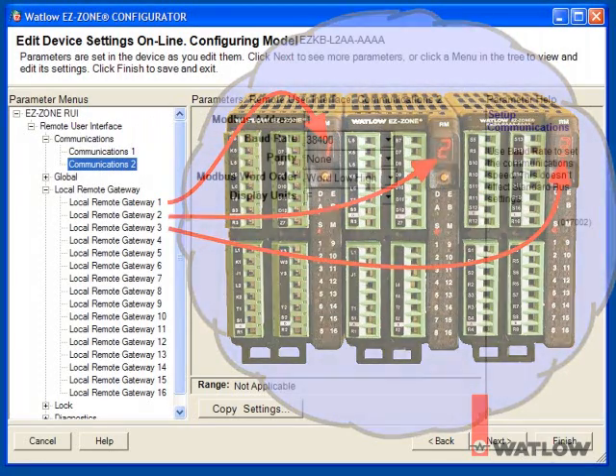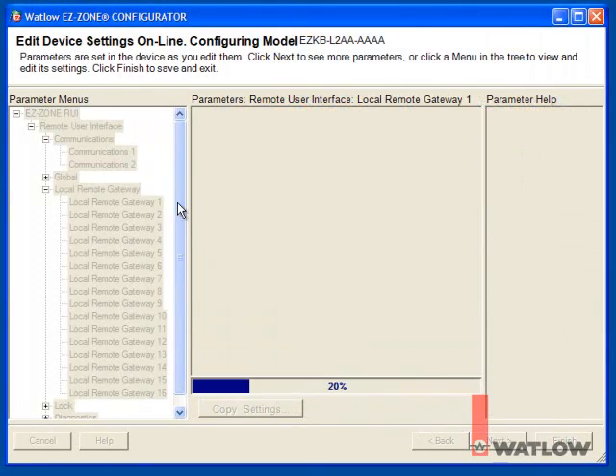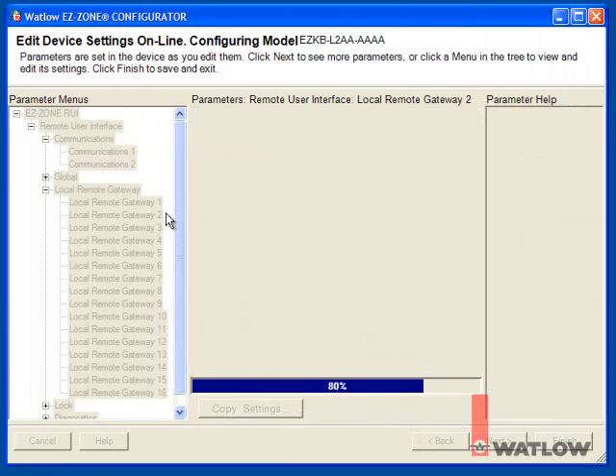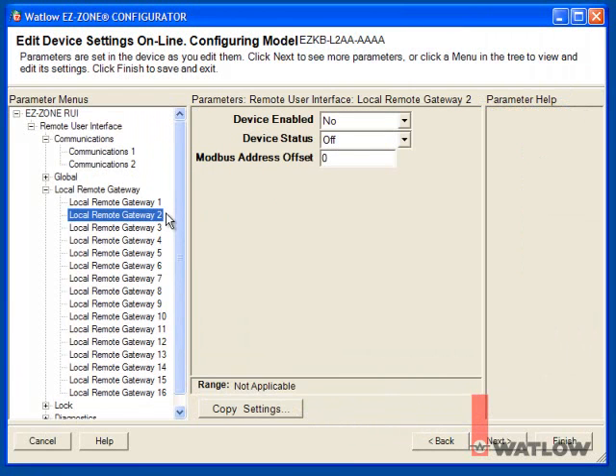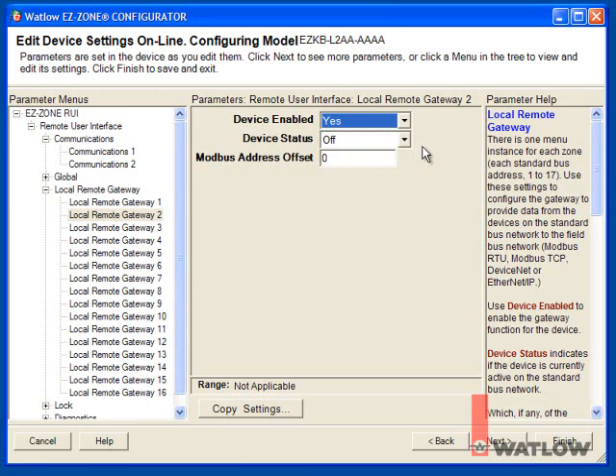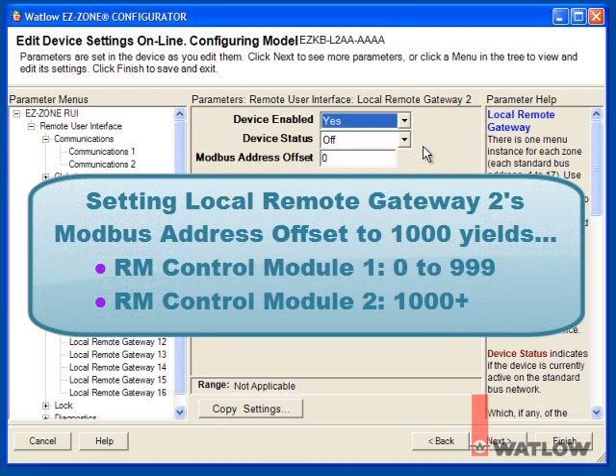For each device, enable it and set the Modbus address offset. The offset for the first controller will be 0. We have to carefully consider the offsets for the other two controllers because these offsets determine how many controllers will be able to communicate via the gateway and which parameters you'll be able to access in each. The offset we set for the second controller limits the range of addresses that can be accessed via the gateway in the first controller.